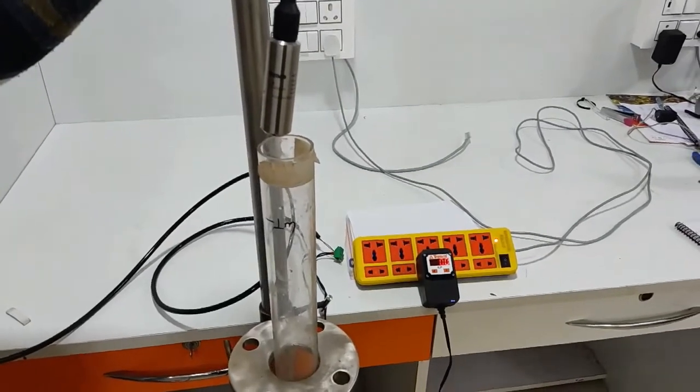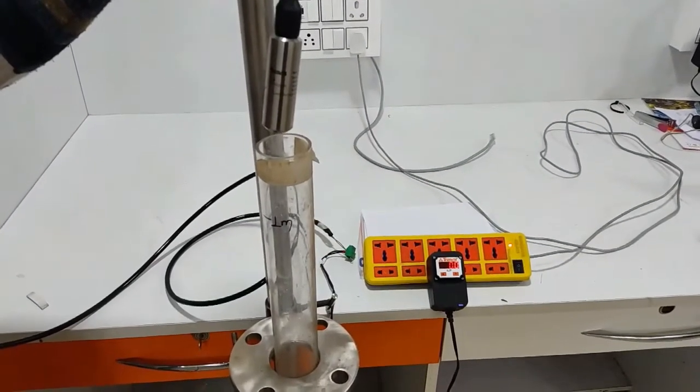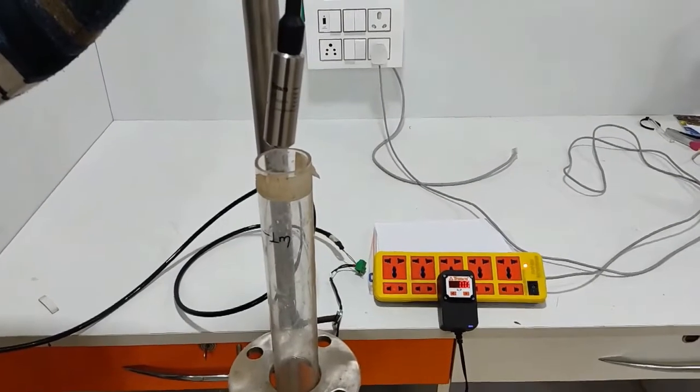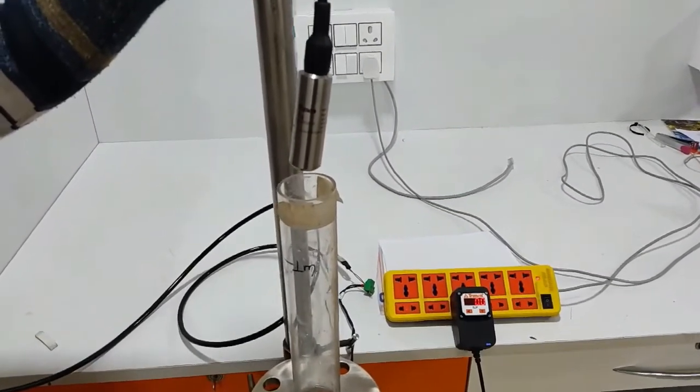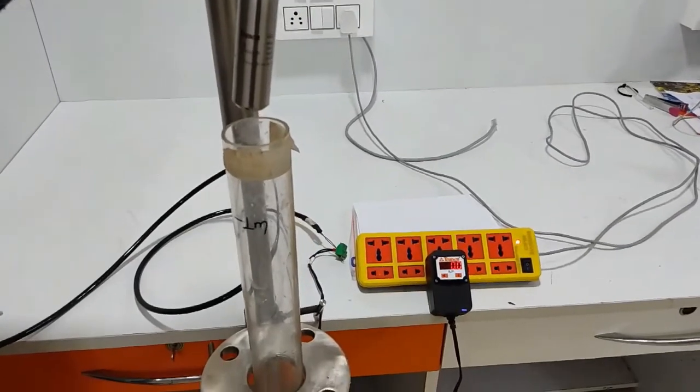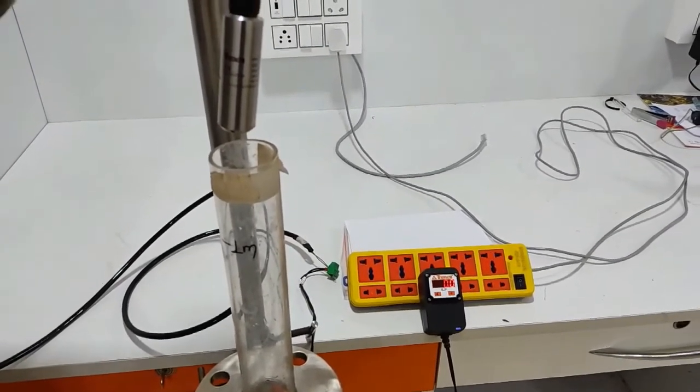As you know, our sensor is calibrated from 0 to 1 meter. We are checking it in air for 4 mA. As you see, the sensor is in air and our display is showing 0% for 4 mA.